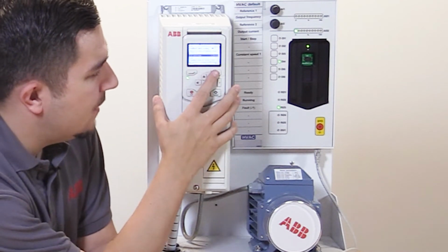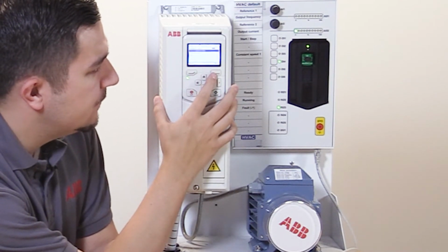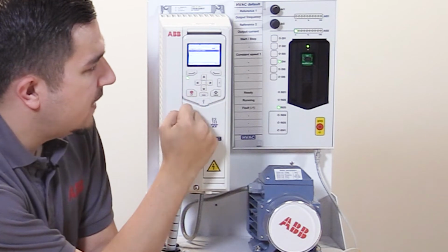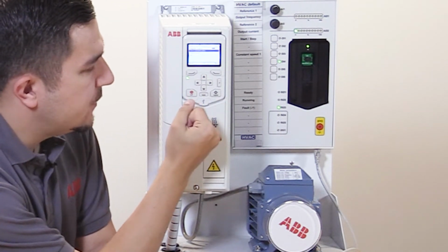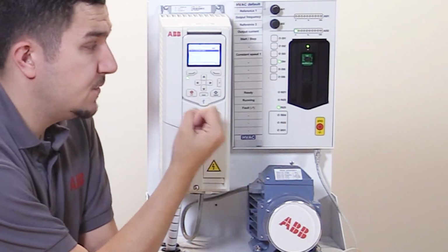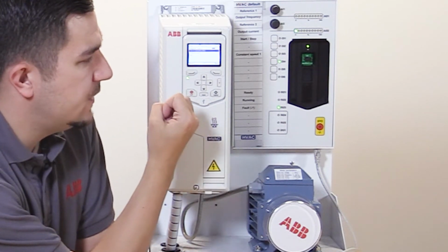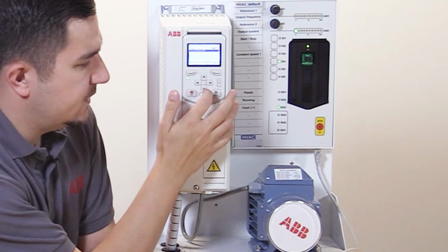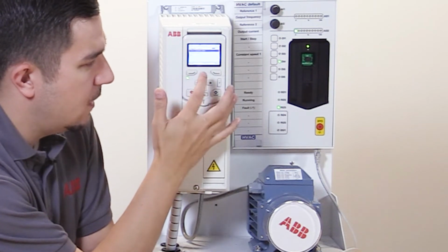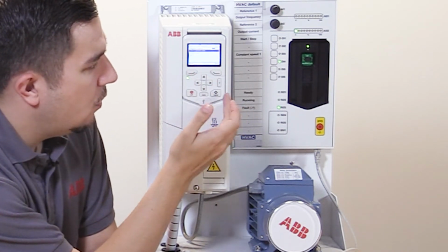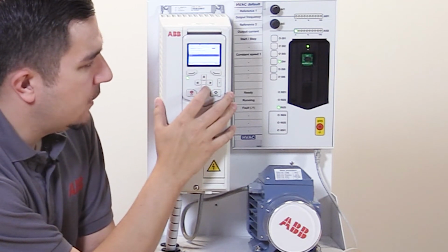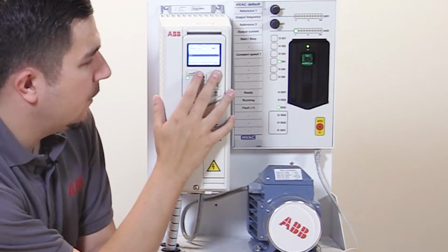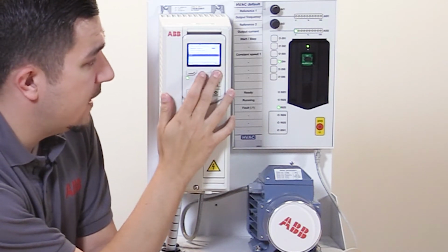Once we're happy with that, we can go on to the next, and then we now define what our set point source is going to be. There are 3 different ways we can do this. We can do it using a constant value. We can do it using the control panel, so we could set it using the up and down arrows on our control panel, or we can set it using analog input 1. So I'm going to be a bit quirky. I'm going to go with analog input 1 on this, and once you're happy with that, we go on to next.